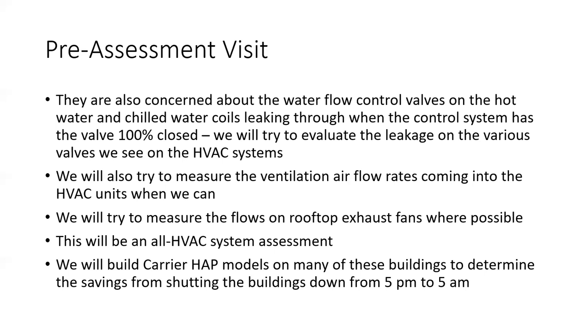Another idea is on some of these large air handlers that you can actually physically walk into, we would take a vane anemometer in and a tape measure, and we would measure the cross-section area of the louvers, estimate the louver position, and try to measure the amount of outside ventilation air that was actually being pulled into the unit. I know we can do that on some of them. Some of them we probably won't have access on, and all we can do is the best we can do.